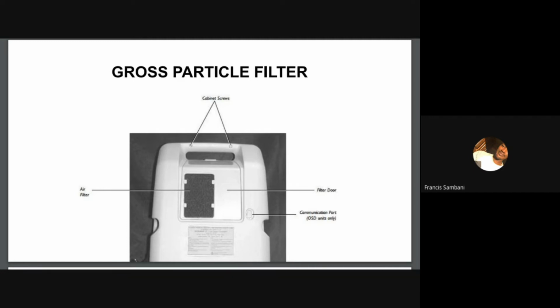And you should make sure that it is securely tightened, because if it is not secure enough, you set your flow at 5 liters per minute, for example, but the patient doesn't end up getting the 5 liters per minute just because some air is leaking. So you should make sure that you don't have any leaks from the outlet port of the oxygen concentrator to the nasal cannula itself.